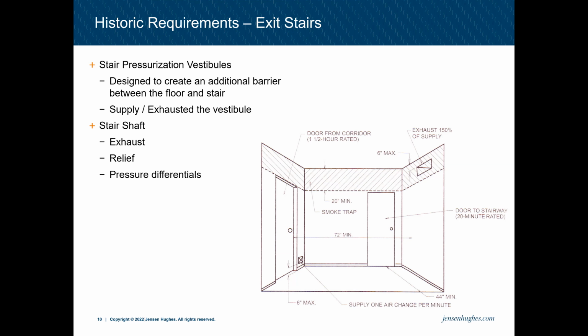An example of this is, has everyone heard of the Grenfell Tower in England? There was a high-rise building in England, and in 2017, they had a fire up its facade, and it was a tragic fire. But they had one stairwell, and they had a smoke control system within the stair itself, but it was a smoke exhaust system. And part of what it was capable of doing was exhausting a fire out of one flat or one apartment, but it was overwhelmed when the fire spread to a second flat. It couldn't handle the exhaust of the smoke outside that shaft anymore, and so it tended to fail.